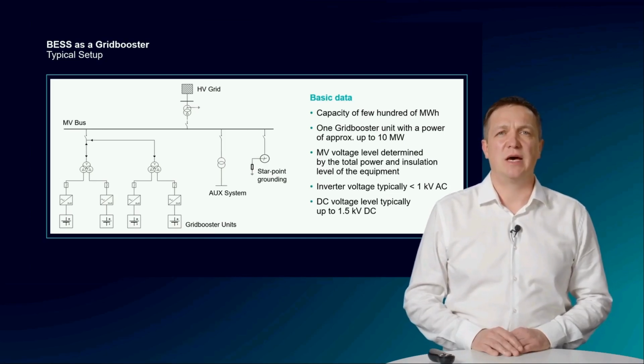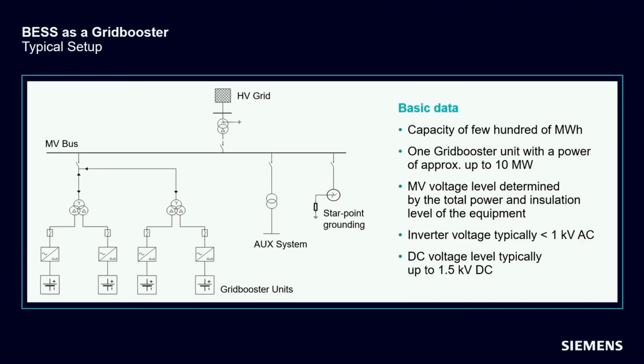As you can see on the slide, a typical setup of a grid booster consists of a number of grid booster units. Each unit includes several battery racks, providing a DC voltage of up to 1.5 kV DC, and is connected through an inverter to the low voltage AC system. Using a 2 or 3 winding step-up transformer, a so-called grid booster transformer, the low voltage system is connected to the medium voltage level. One grid booster unit provides a power of approximately 10 megawatts. And the main limiting factor here is the maximum available power rating of the dry type power transformers.